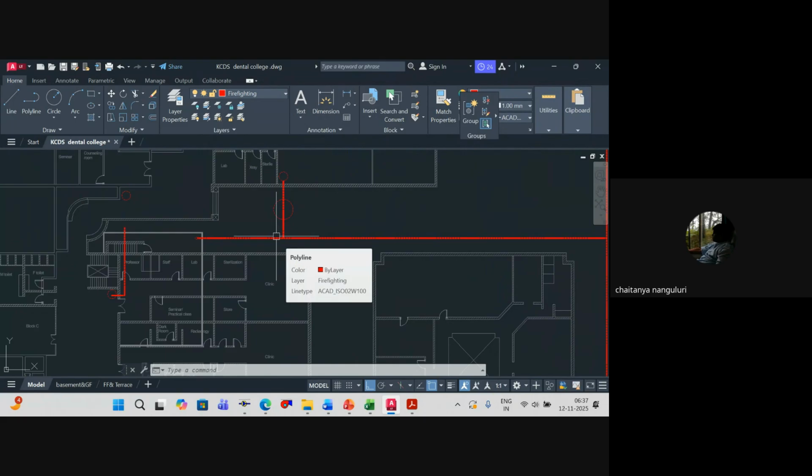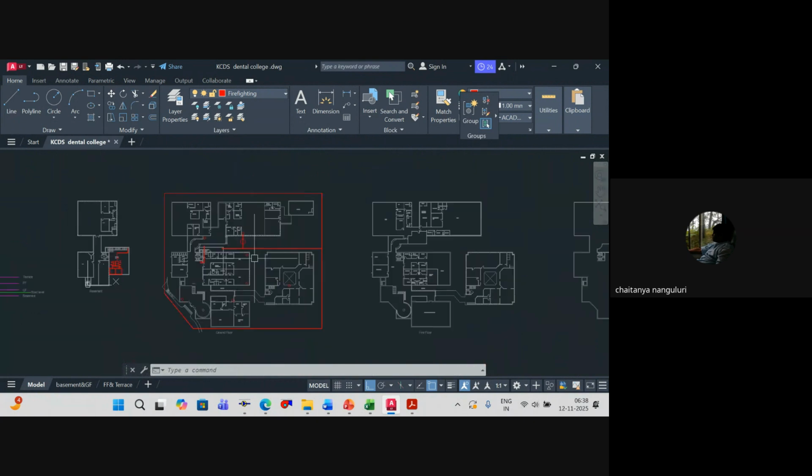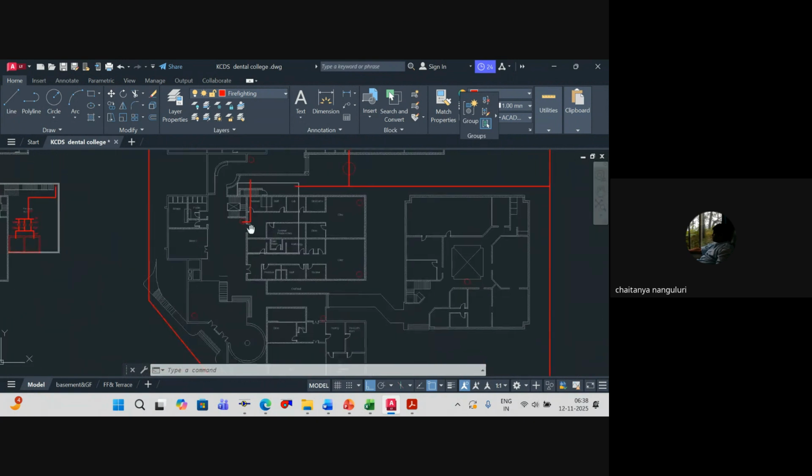You can take two separate pipes from the delivery manifold if you want. But that is generally done when you have two separate pump systems. When you have a separate sprinkler pump and hydrant pump, then you exercise that. Understood?